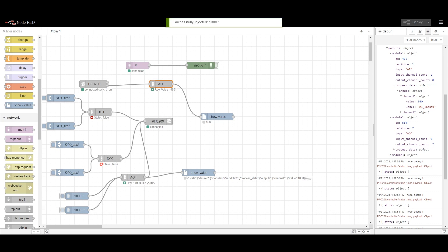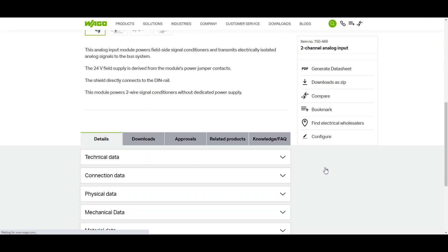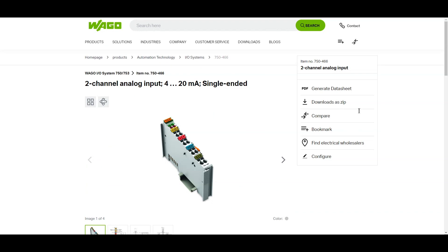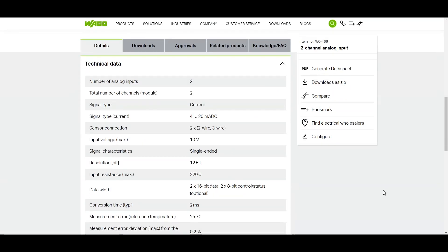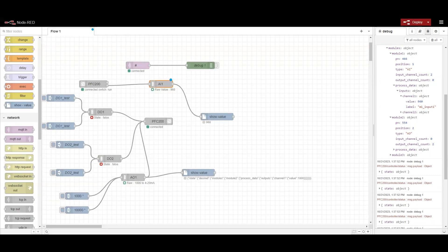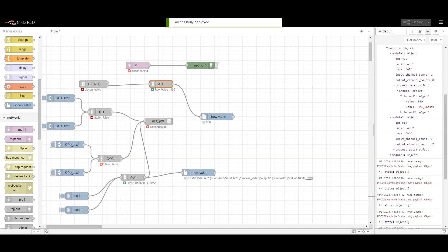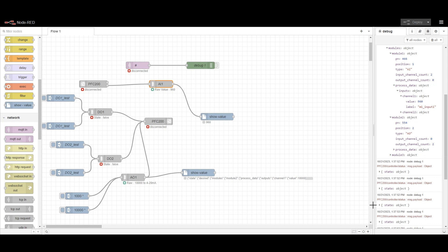Even if I switch between 12-bit and 16-bit here it does not impact much visually, but it is good practice to set the correct resolution matching your card. The resolution can be found in the technical data sheet of the card — if you see here it shows 12-bit resolution, so we configure the resolution as 12-bit. In the debug node you can also find details about what card is connected, such as card type codes like 466554.